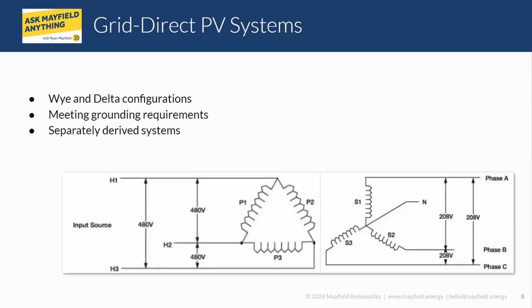So the term isolation transformer is confused a lot of times on really what that means. An auto transformer is just basically a straight through windings, and based on where it's tapped off of, you'll have a voltage change, but there's no isolation there. So the current limiting function and the protection there is not really there.